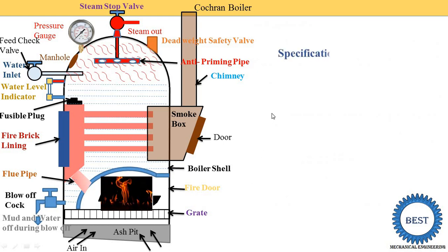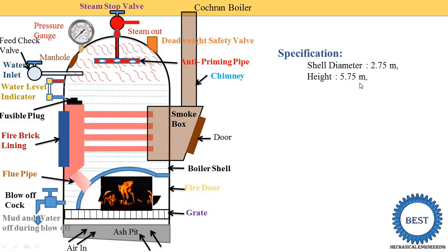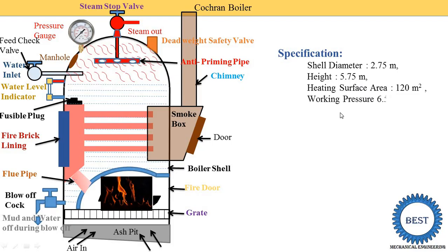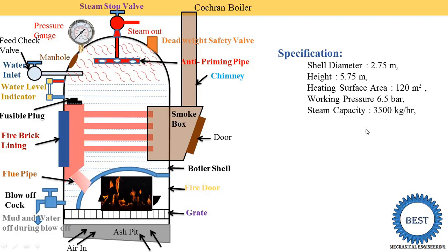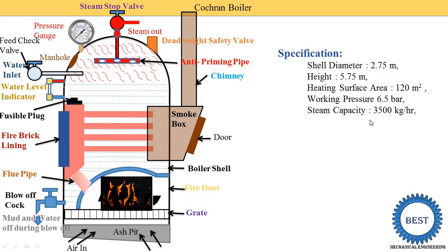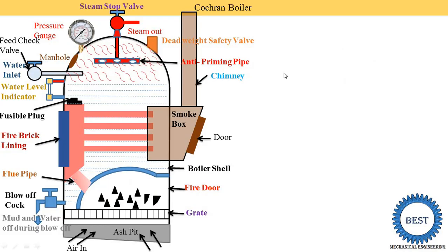The specifications of the Cochran Boiler are: shell diameter 2.75 meters, height 5.75 meters, heating surface area 120 square meters, working pressure 6.5 bar, steam capacity 3500 kg per hour — meaning the Cochran Boiler produces 3500 kg of steam in one hour — and efficiency 70 to 75%.